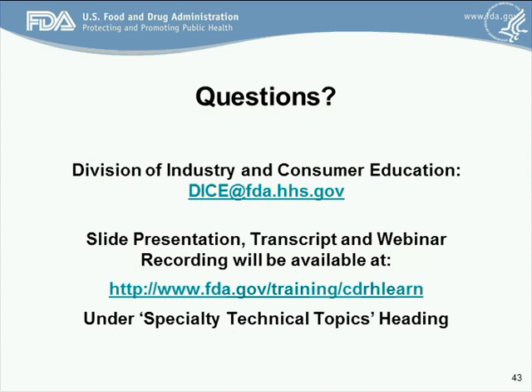The next question comes from Pamela Barrows of HCM. Regarding pyrogenicity — the slide said that alternatives to batch release are acceptable if you have a sampling plan and a justification. Would FDA expect a risk assessment per AAMI ST72, or would other formats for justification be acceptable? The response: it really depends on what the justification is and how well it's substantiated, so contact the branch of the division reviewing that particular device type to discuss it with them.